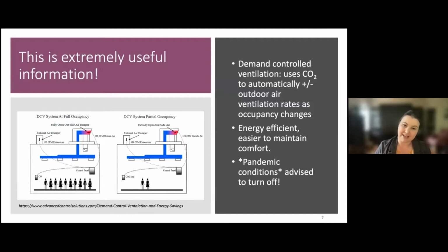When the building is crowded, like here on the left, and full, CO2 levels are high, the control panel tells the outdoor air damper to open right up, bringing in a lot of fresh air to meet that ventilation demand. However, as occupancy decreases, there's a corresponding downward trend in CO2 level. The control panel registers that and starts to close the damper, decreasing the outdoor air fraction.